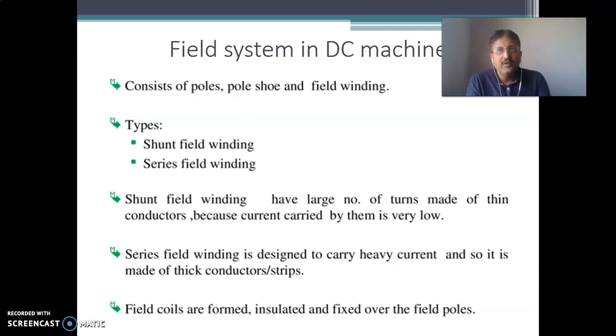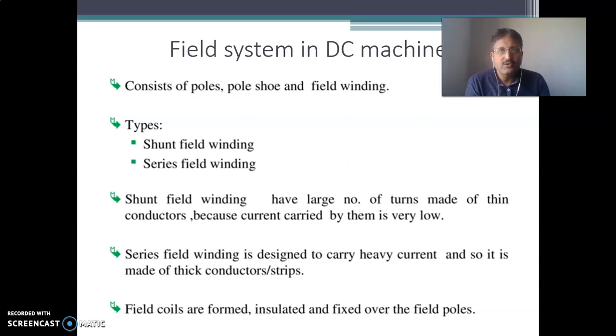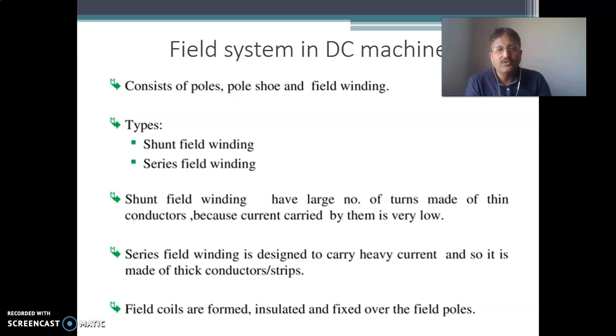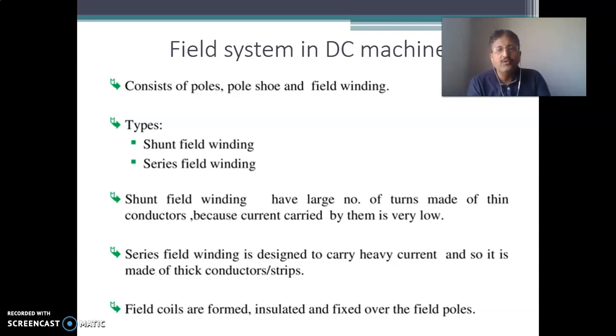Series field winding is connected in series with the armature. So it has to carry the entire armature current or load current. Therefore it is made up of thick cross section conductors or strips and it is made up of few number of turns.